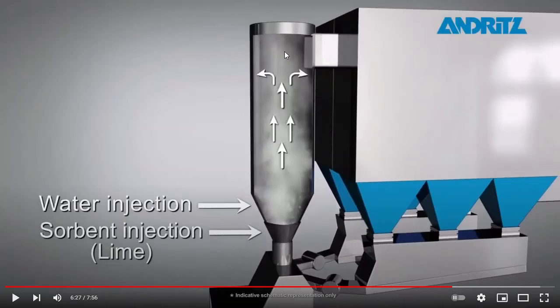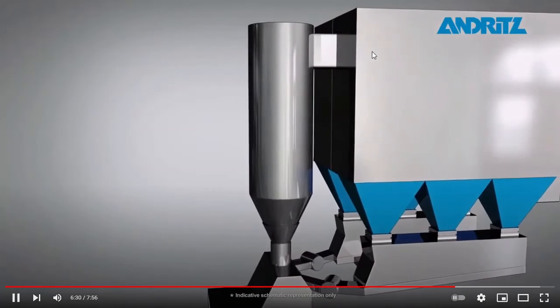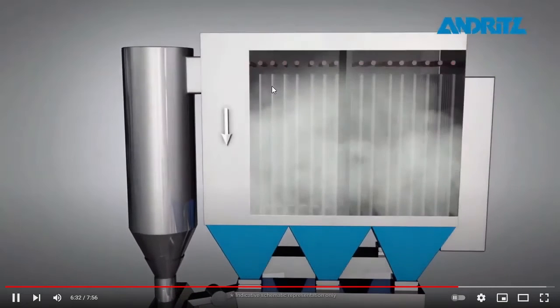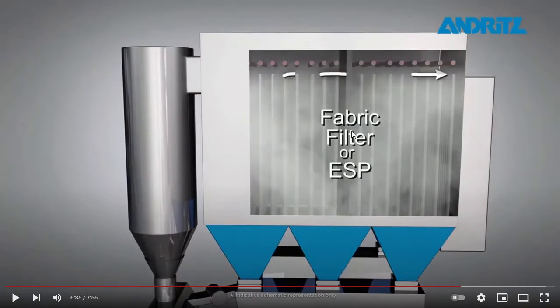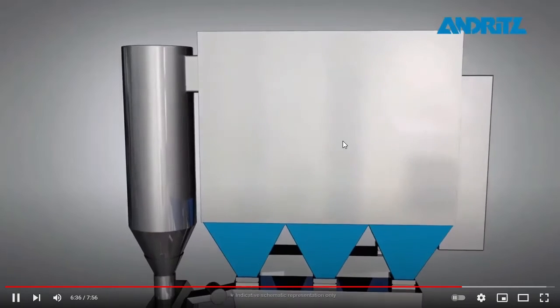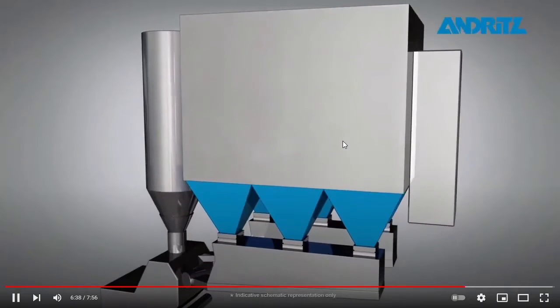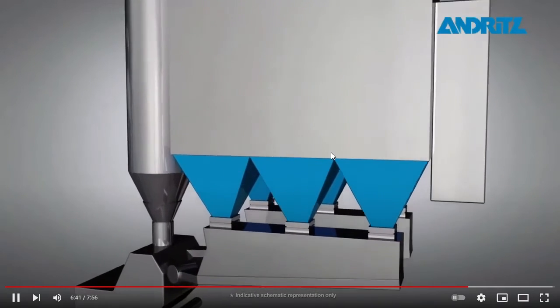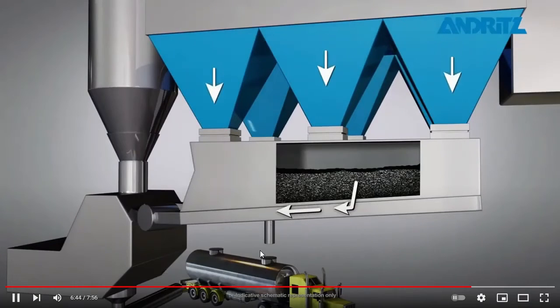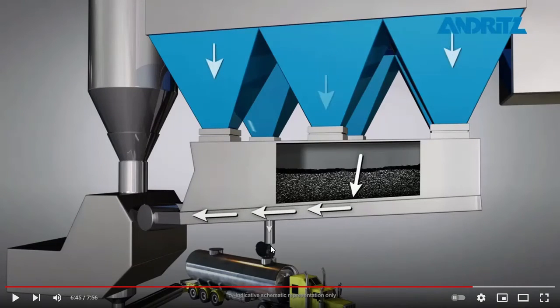So now the final thing is to get that ash out of there. That's over here in the bag house, right? So it's going to come up here, and it's going to go over there, and then it comes here. So you've got your fabric filter. We said that some people have electrostatic precipitators. We don't have those. All this is basically that big vacuum cleaner bag, right? So it goes in there, and then, I'm not sure what else is on here. Oh, okay, that's them hauling that ash away because that's coming out of the bag house.